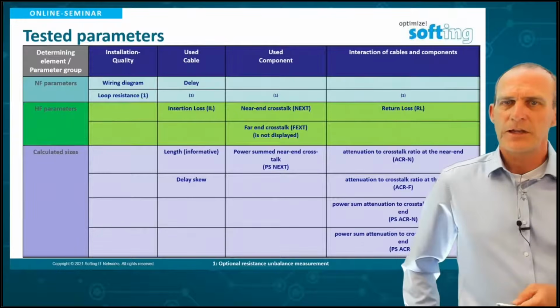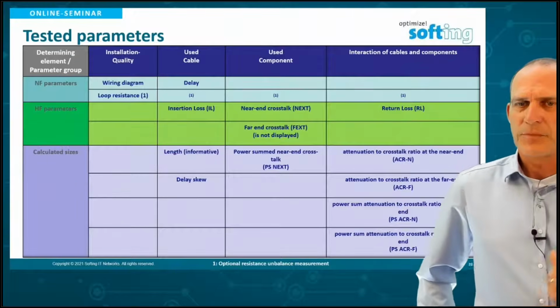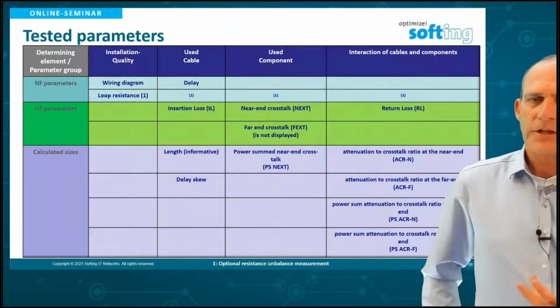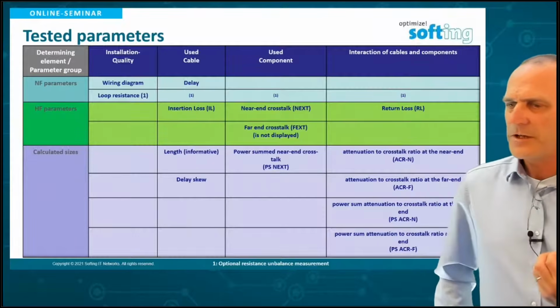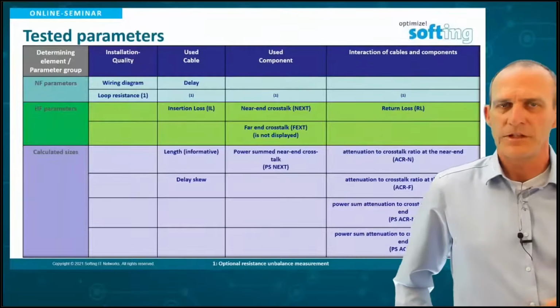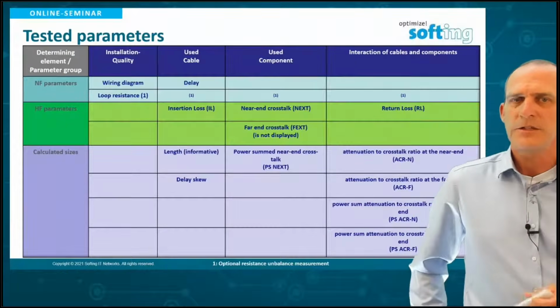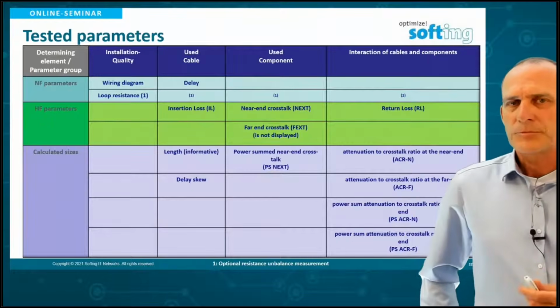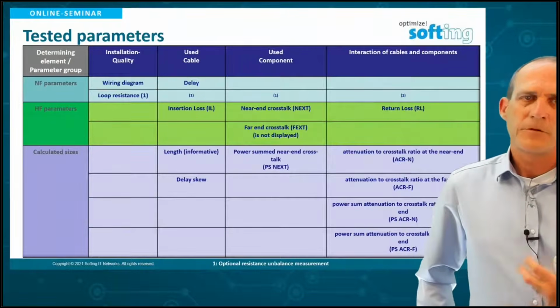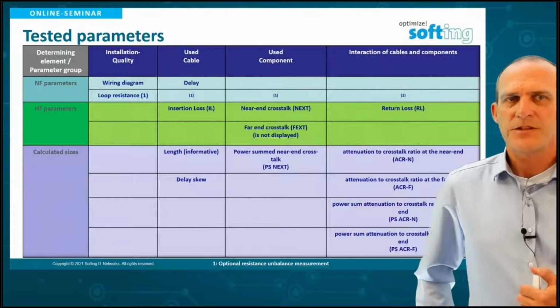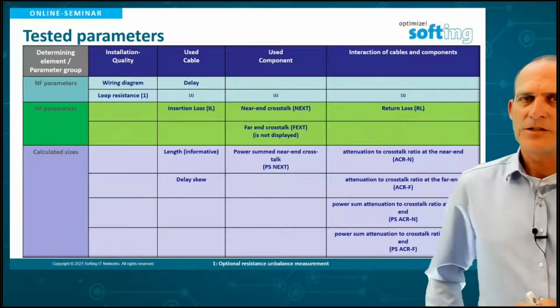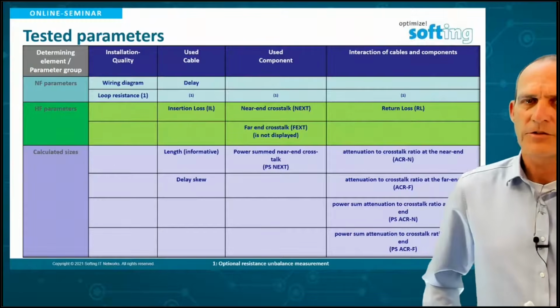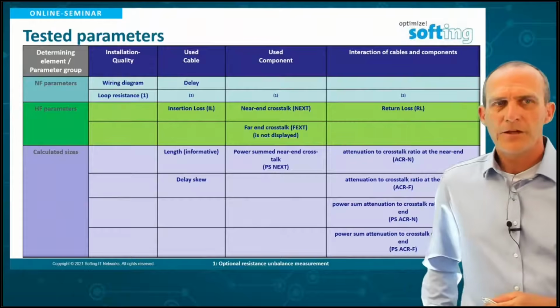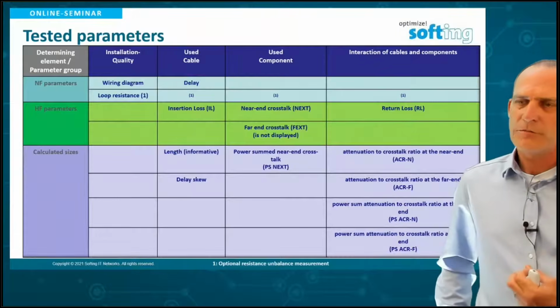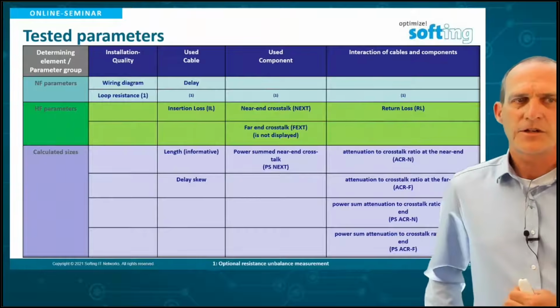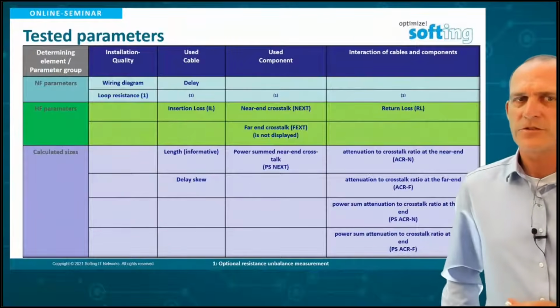And then we have a lot of calculated parameters. Length is calculated, of course. Length in ISO and EN standards is only an informative value, so that's not a pass-fail. Delay skew is a calculated value. Power sum values, power sum NEXT, give you again a good hint on the connectors, if the connectors are good. And then we have the interaction again between components and cables. Calculated values are ACRN, ACRF, and the power sum values of that.